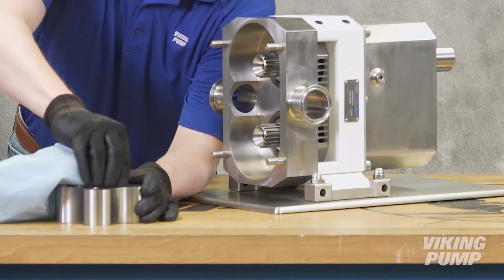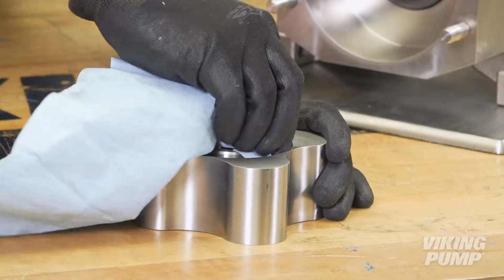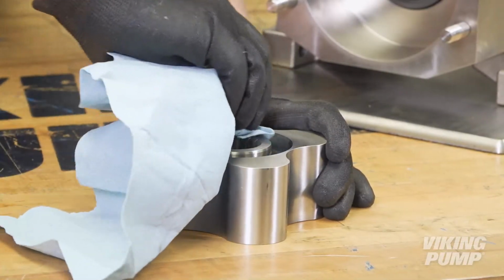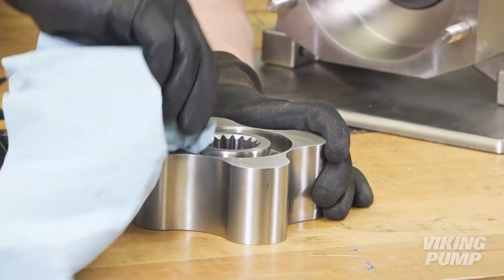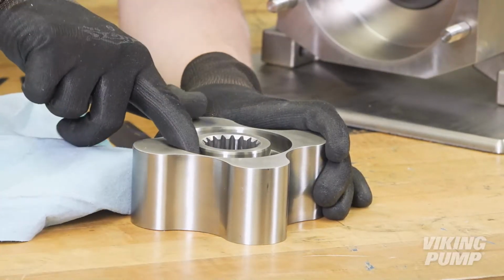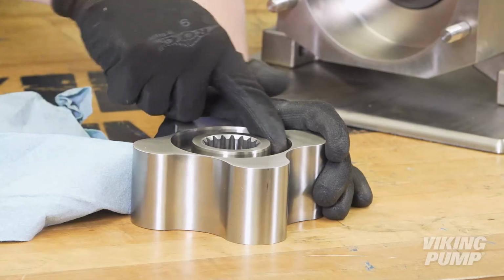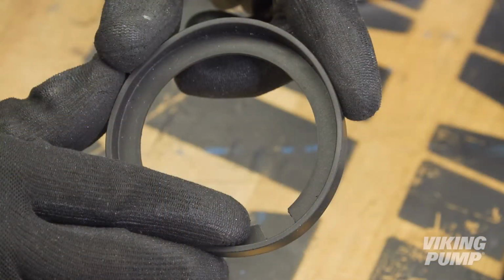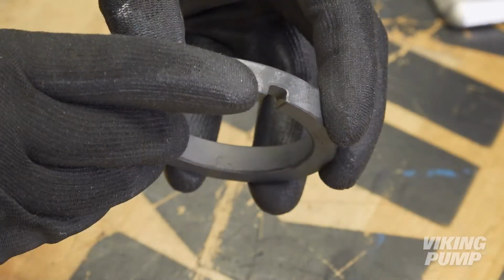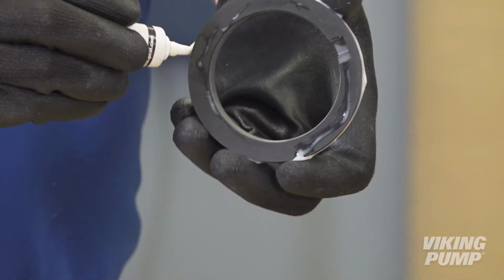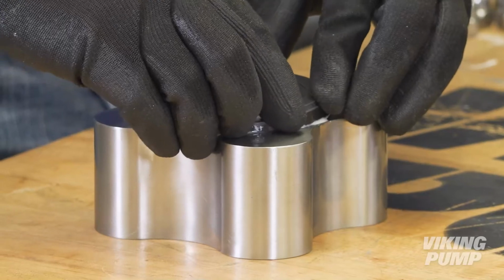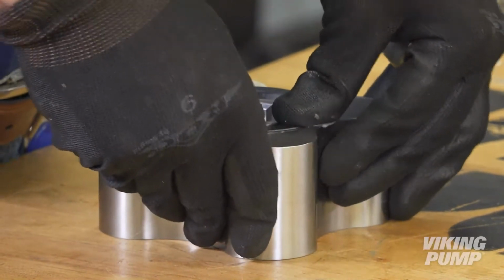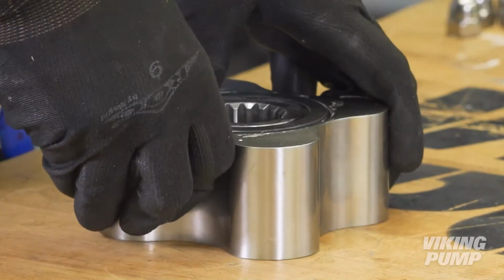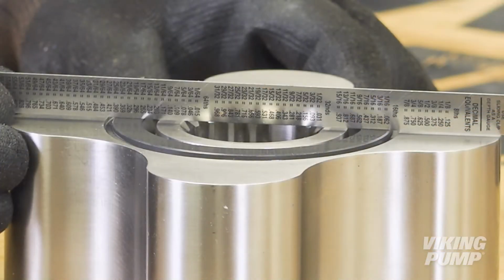Install new rotary seal faces and cups. To do this, place the rotors face down on a clean, non-marring work surface. Inspect the bore to make sure that it is clean and free from debris or damage. Line up the cutouts in the rubber cup and seal face. When included, line up these cutouts with the pin in the rotor bore. Lubricate the cup and press the seal face and cup into the rotor until it reaches the back of the bore. Make sure the face is level and parallel with the back of the rotor.